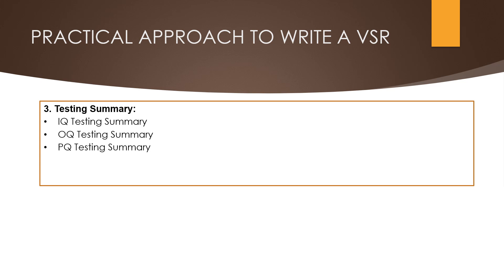Next is the OQ testing summary. Here we need to define the start date and completion date of operational qualification, and the OQ acceptance criteria which meets as per the OQ testing. We also need to define the OQ status — brief details about the OQ protocol number, status of pass or fail, and if any discrepancy is observed, the reference number of that discrepancy.